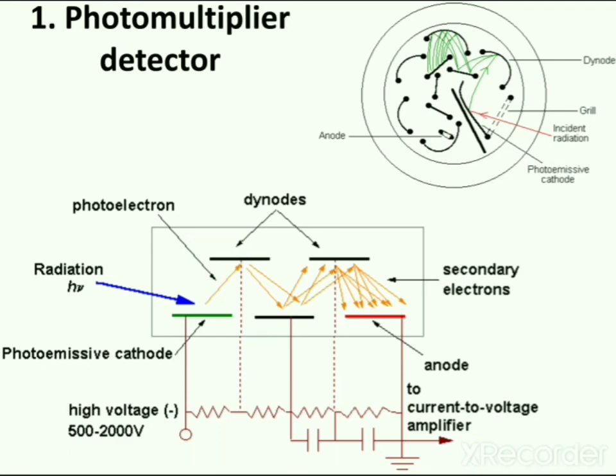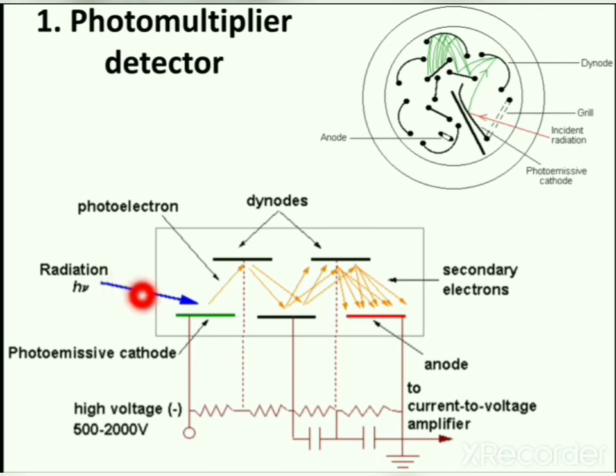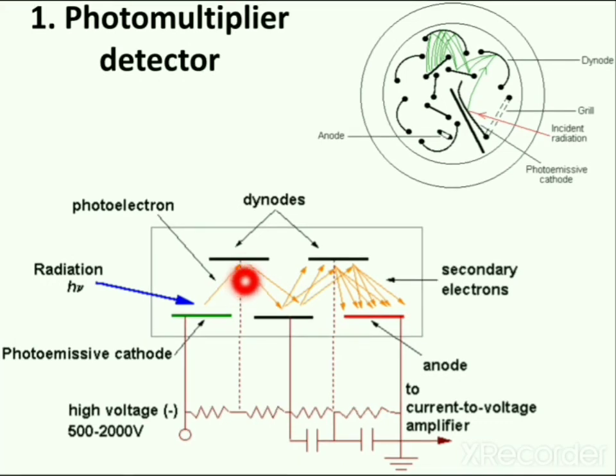The photomultiplier is extremely sensitive to light and best suited when weaker or low radiation is received. When radiation from the sample is incident upon the first photocathode, it generates electrons. These electrons are accelerated toward the dynode chain, with focusing electrodes ensuring photoelectrons emitted near the edges of the photocathode land on the first dynode. Upon impacting each dynode, additional electrons are released and accelerated toward the next dynode, resulting in amplification of the signal produced by the primary electrons. Photomultipliers produce a signal even in the absence of light due to dark current arising from thermal emissions of electrons from the photocathode.